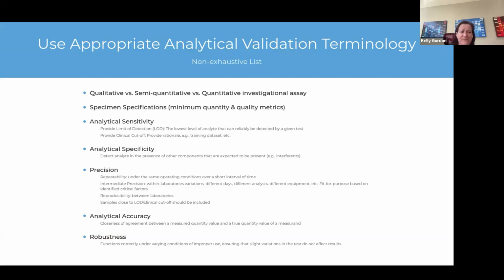Semi-quantitative is more like you have ordinal categories like low, medium, high. So there are 3 buckets, for example, and then quantitative is where you're actually reporting specific metrics, like certain levels of biomarkers. There's a lot more burden to report quantitatively than qualitatively. So for example, if you're doing a precision study and it's a qualitative assay, FDA is going to be looking for positive percent agreement and negative percent agreement across those 2 categories, versus quantitative, where they may ask for some more.